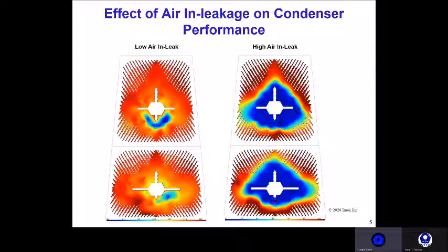What is interesting on the left is the pattern of airbound zone below the center of the bundle where the air offtake pipe is. This smiley face pattern is typical for the air binding in the Westinghouse design. It is worth noting that before we ever had the chance to install temperature arrays on a Westinghouse, we would see tube plugging in this same shape during condenser inspections, which indicated that it was inherent to the design. We observed this particularly in units with copper-bearing tubes and as a result of ammonia grooving. As a side note, Intek has successfully retrofitted these styles of condensers to mitigate the design-related issue.